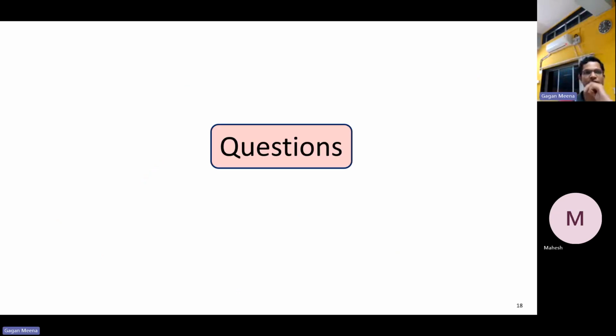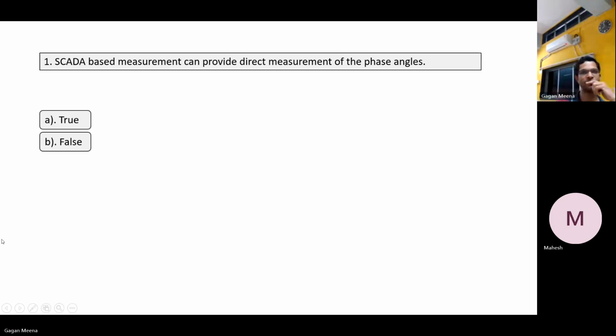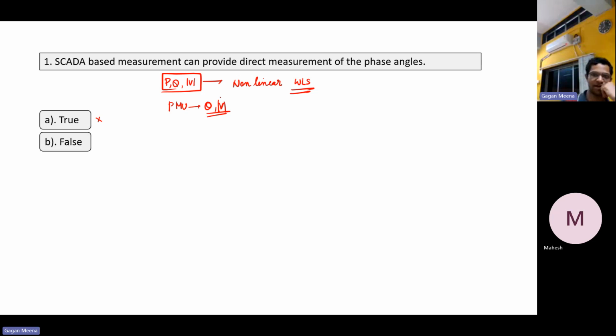Now we will move to the questions. First question is: SCADA measurements can provide direct measurement of phase angles. Is it true or false? Okay, Mahesh is saying it is true, but that's not correct. It is false. SCADA cannot provide a direct measurement of phase angle. SCADA provides us P, Q and voltage magnitude only. But PMU can provide us the data for voltage magnitude and angle directly.